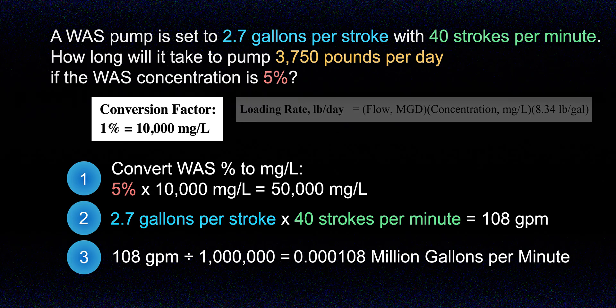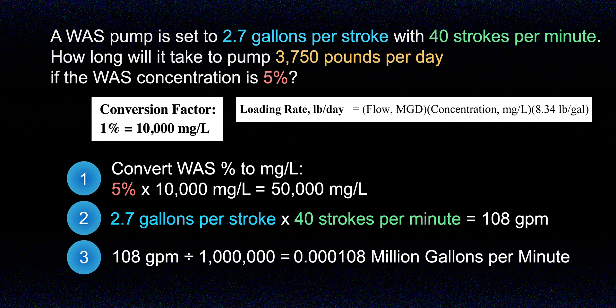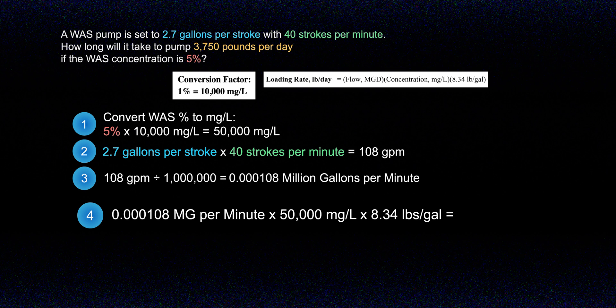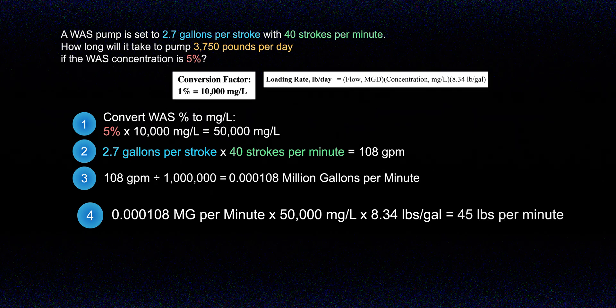This allows us to put it into the loading rate formula shown on screen. Although the formula shows million gallons per day, the per-day part is not always necessary — the time unit could be any unit of time, and this formula can also be used to calculate mass in pounds with no time unit at all. The important thing is that the flow or volume must be converted to million gallons. In step 4, we use the loading rate formula: 0.000108 million gallons per minute multiplied by 50,000 mg/L multiplied by 8.34 pounds per gallon gives us 45 pounds per minute.